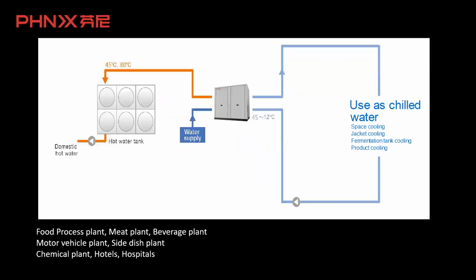The second one, as you can see, is this water-to-water heat pump working independently. On the right side, the water temperature is from 12 degrees to 45 degrees, while the left side is 45 degrees to 80 degrees, and it is used in food process plants, meat plants, beverage plants, side dish plants, chemical plants, hotels, and hospitals. So this application is simple, right? Yeah, it's similar to the last page. But the total difference is that the Phoenix water source heat pump in this application can work independently.